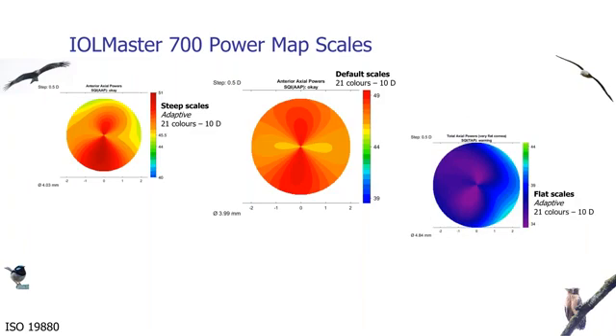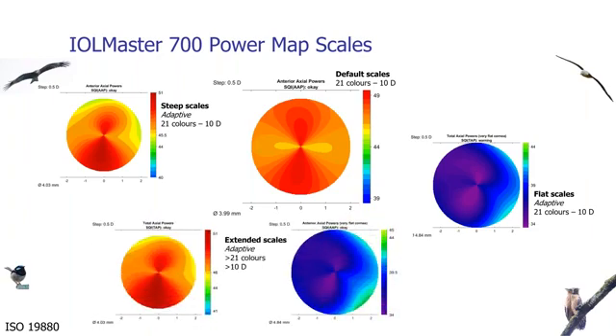This is an example of axial power maps. It has a default scale with 21 color steps. This is what happens for most corneas within the normal range. If the cornea is very steep, the scale will move up keeping 21 colors, 10 diopter scale at half diopter steps. If it's too flat, the scale will move down. For unusual corneas with power spread much more than 10 diopters, we have more than 21 colors in half diopter steps.